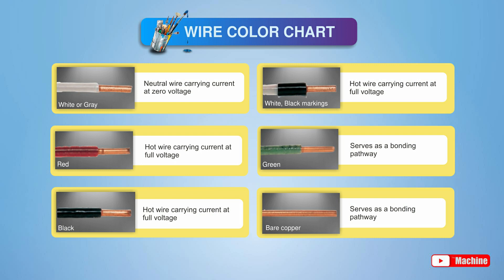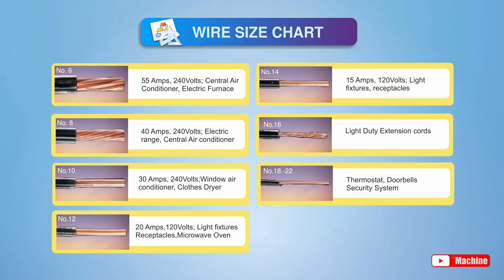Individual wires are color coded to identify their function. In some circuit installations, the white wire serves as a hot wire that carries voltage. If so, this white wire may be labeled with black tape or paint to identify it as a hot wire. Wire sizes are categorized by the American Wire Gauge system. The larger the wire size, the smaller the AWG number.